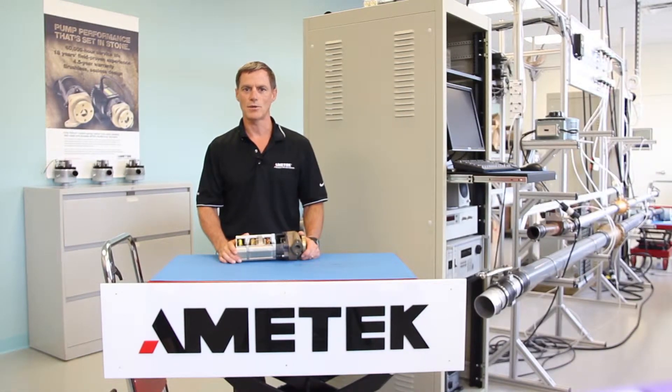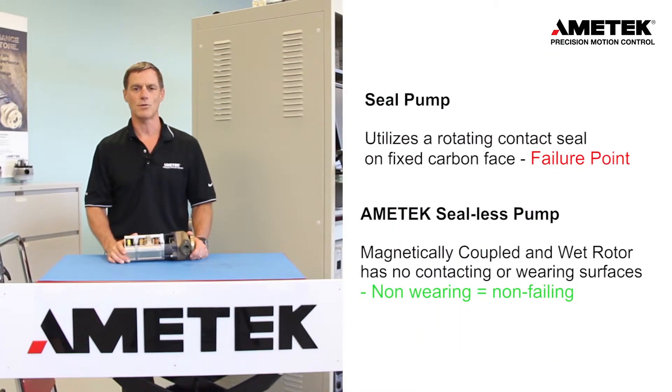The pump head can use either a seal or Seal-less type technology. A seal pump utilizes a rotating contact seal with a carbon and ceramic surface, which is the primary failure point and results in leaks. A Seal-less pump utilizes a magnetically coupled technology, and there are no contacting surfaces or wear points other than the bearing system.